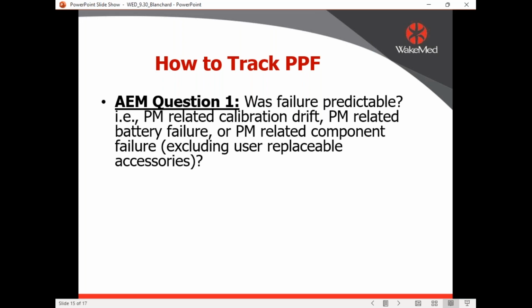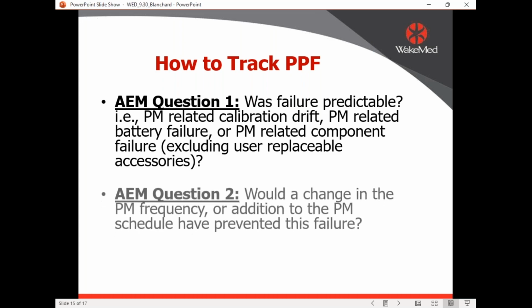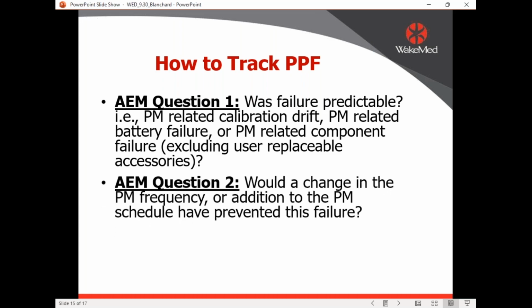PM-related calibration drift, a PM-related battery failure, or a PM-related component failure? So if we have a device that's on AEM and it comes down because the filter's clogged up, because we're not changing filters anymore, then somebody would say, yes, that was a predictable failure. We should have been changing filters. Same thing with batteries. Probably should be changing batteries. They're going to fail. So anything that has a shelf life, you should be changing it out or doing some sort of maintenance on it.